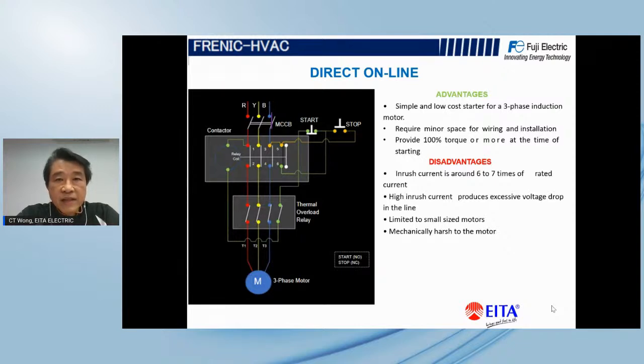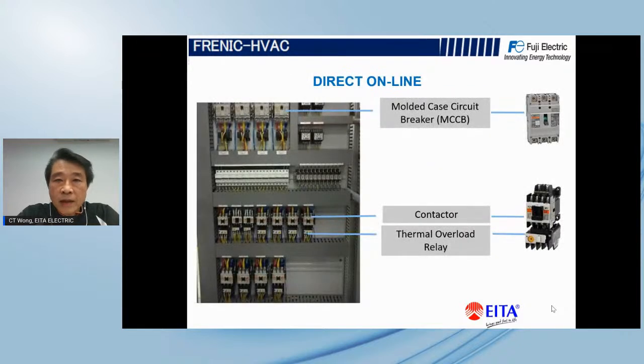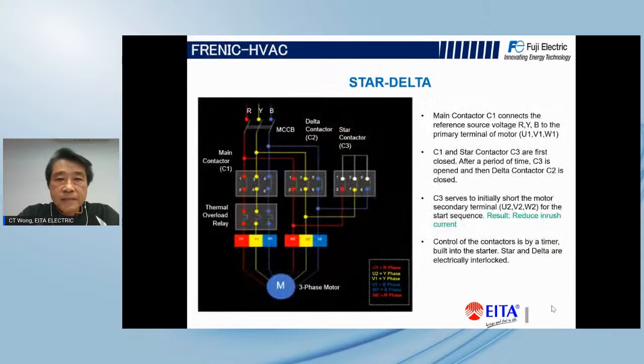The disadvantage of direct online, as I said, is that the inrush is high, around 6 to 7 times the rated current. Because of the inrush, sometimes there will be excessive voltage drop in your power line. It will also be mechanically harsh on the motor because full voltage is energized to the motor. You can see the actual pictures inside the panels with the direct online. You have many circuits over there.